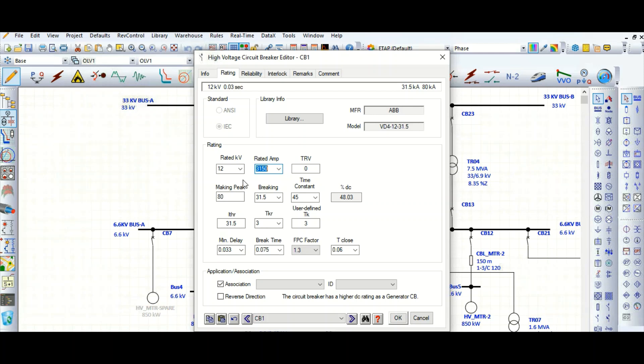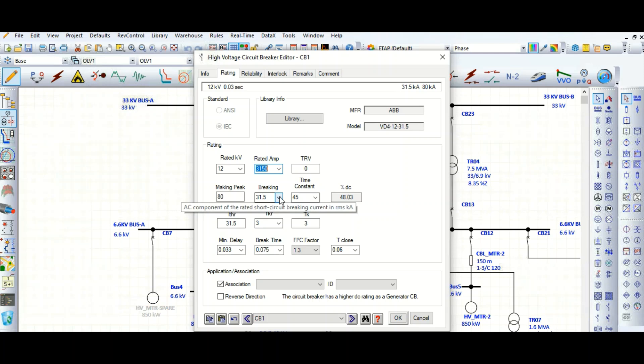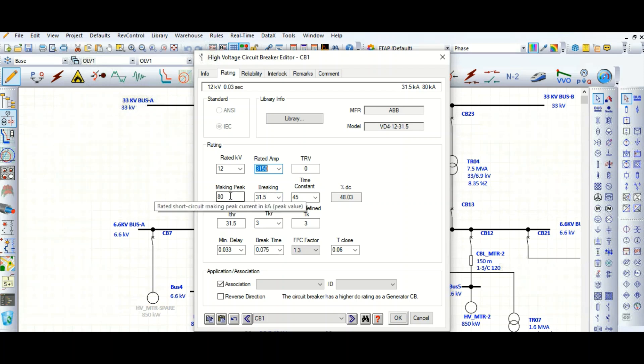That making peak withstand capability is 80 kA. Here is the breaking capacity — in case of any fault, the circuit breaker trips and must be capable of breaking the short circuit fault current. That magnitude is 31.5 kA rms, and 80 kA peak. So 80 kA is the peak value and 31.5 kA is the rms value.